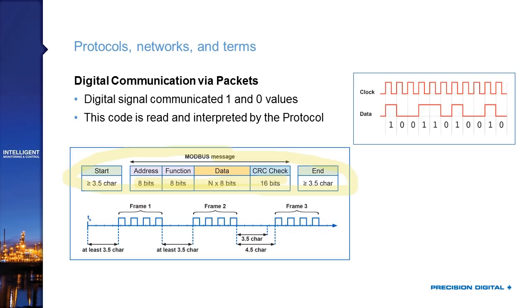Devices string all those ones and zeros together first into a Modbus message and then into an entire Modbus packet. The Modbus protocol explains how to decode those ones and zeros. A device reads the incoming bits and identifies the start characters, a Modbus address, a function code, and a bunch of data. The ones and zeros are detected, strung together, and that gives commands back and forth between different Modbus devices.